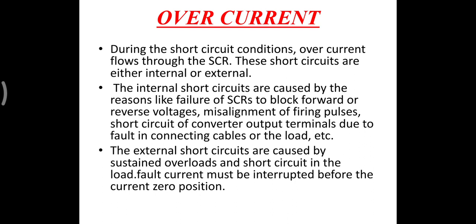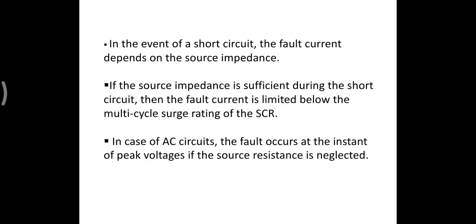And coming to the second one, external short circuit. An external short circuit is caused on the load side, or if there is an overload on the SCR, it is also considered an external short circuit. Because of the overloading, high currents are flowing through the SCR. So this is also considered an overcurrent from the external side. These short circuits cause fault currents. These fault currents mainly depend upon the source impedance.